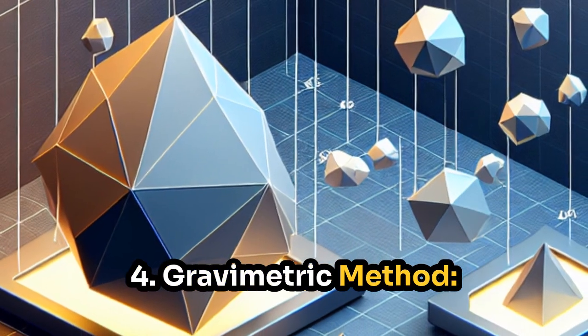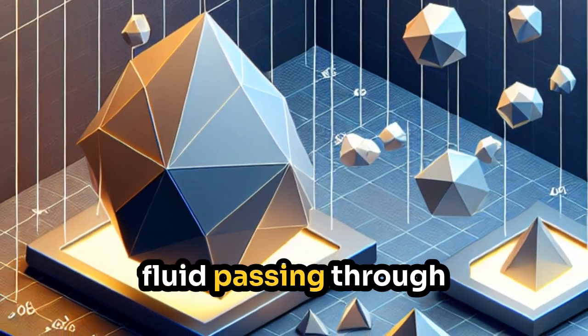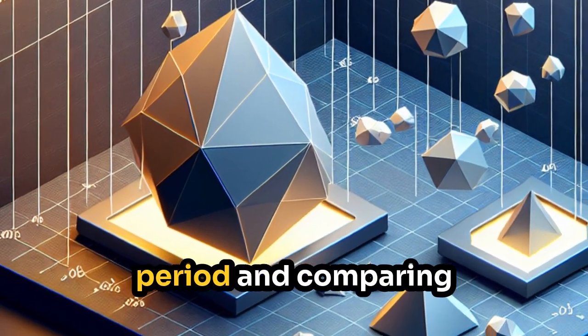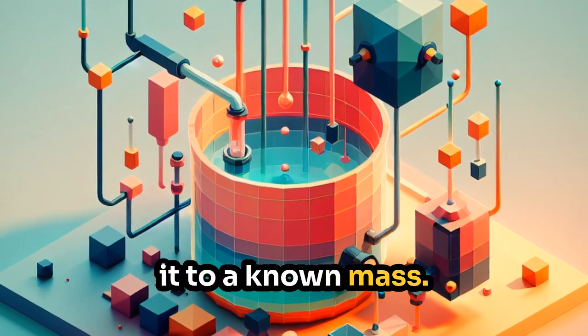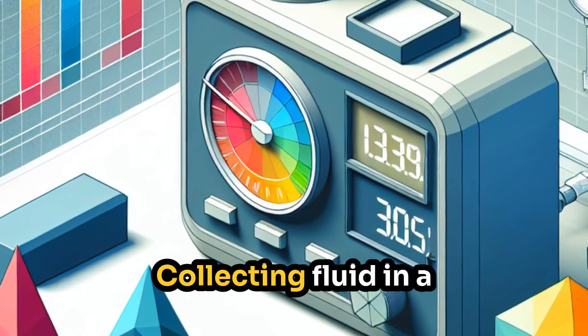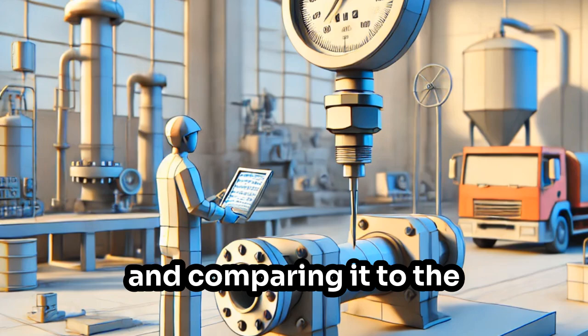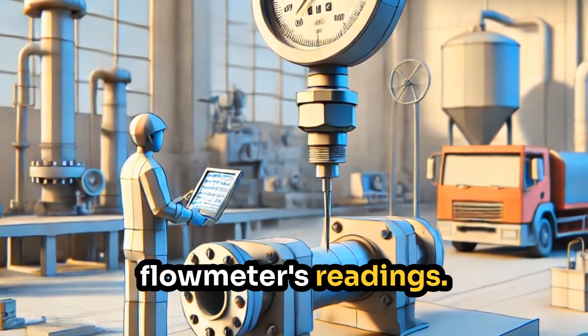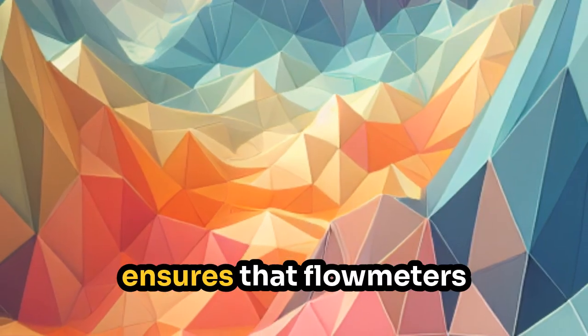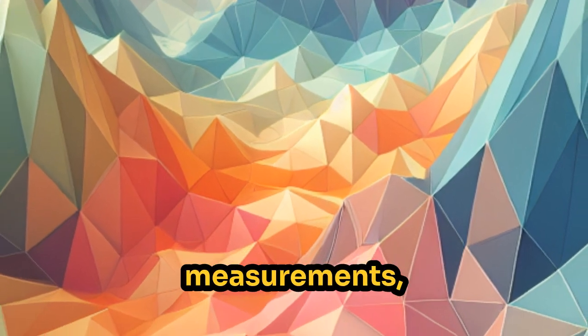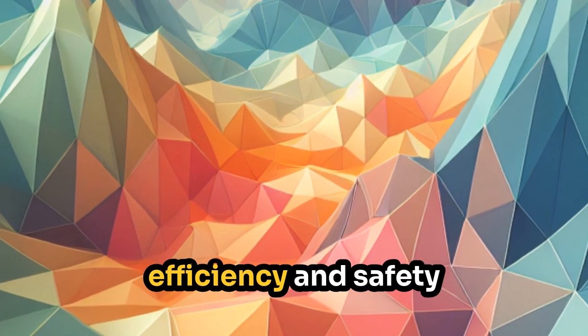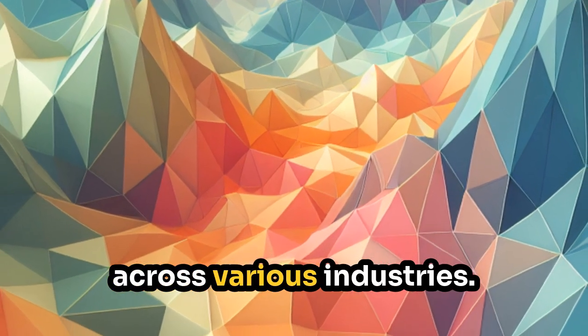4. Gravimetric method, measuring the mass of fluid passing through the flowmeter over a set period and comparing it to a known mass. 5. Volumetric method, collecting fluid in a calibrated container and comparing it to the flowmeter's readings. Regular calibration ensures that flowmeters provide accurate measurements, enhancing process efficiency and safety across various industries.